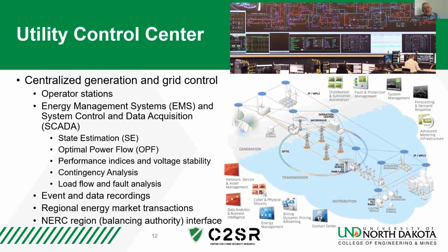Utility Control Center is the brains of the utility. Inside there are a number of redundant computer systems and operator stations. The energy management system and the SCADA system are running on those computers. So we have the state estimator running the optimal power flow, contingency analysis, and as necessary, operators can use load flow and fault analysis to make predictions about what's going to happen with the current system. Also very important is our performance indices are determined for the system based on the state estimation data and provided to the operators so that they know if they're meeting performance targets.